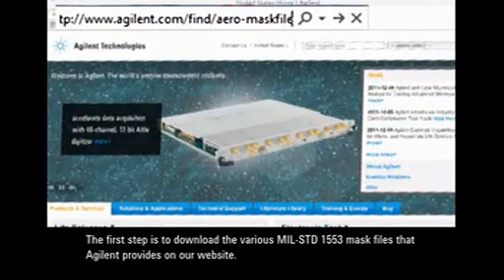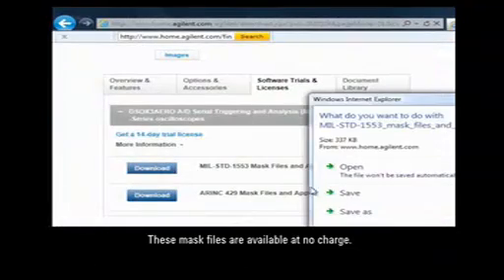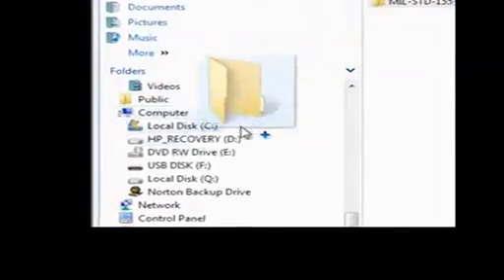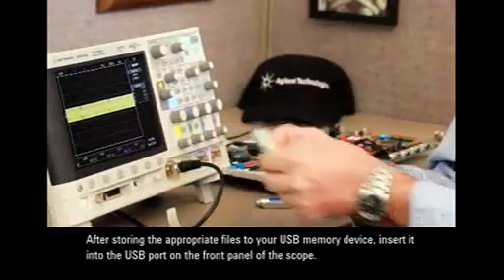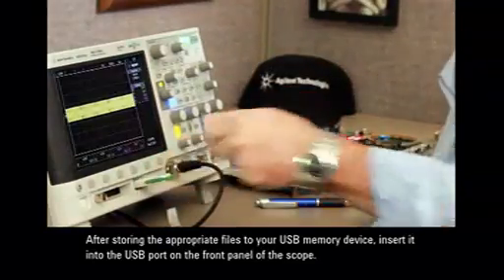The first step is to download the various MIL-STD 1553 mask files that Agilent provides on our website. These mask files are available at no charge. After storing the appropriate files to your memory stick, insert it into the USB port on the front panel of the scope.